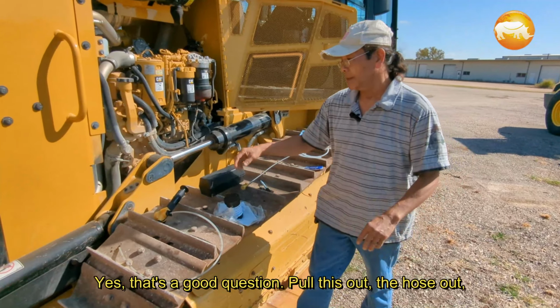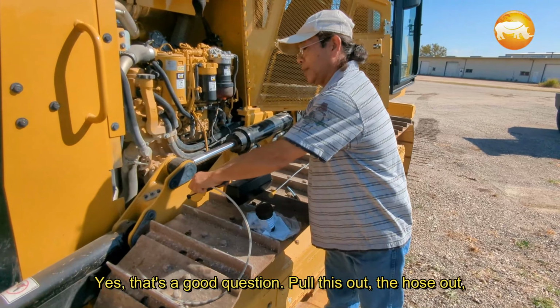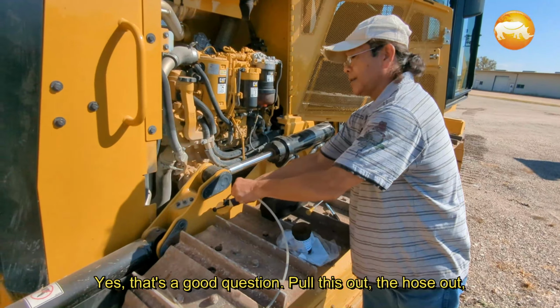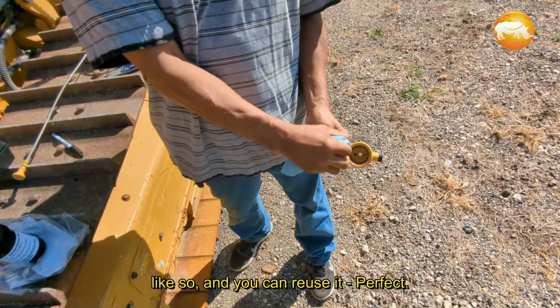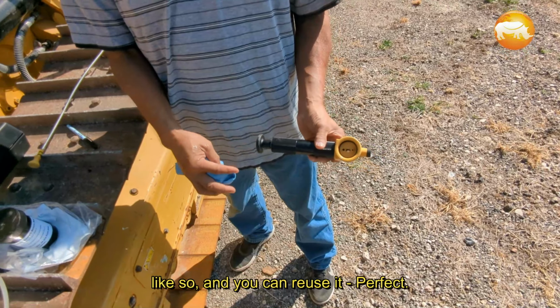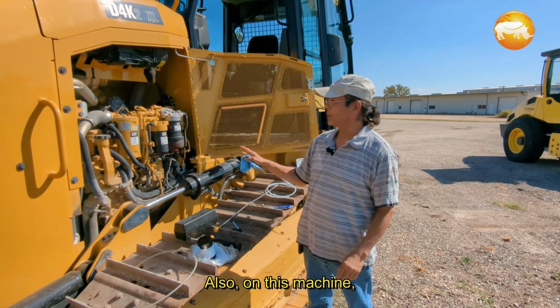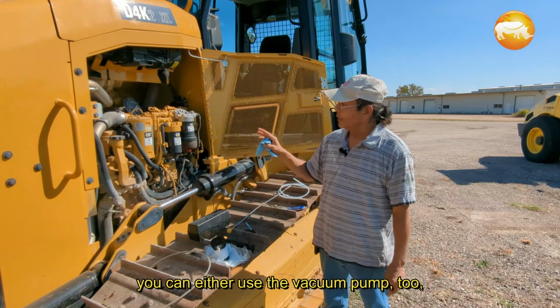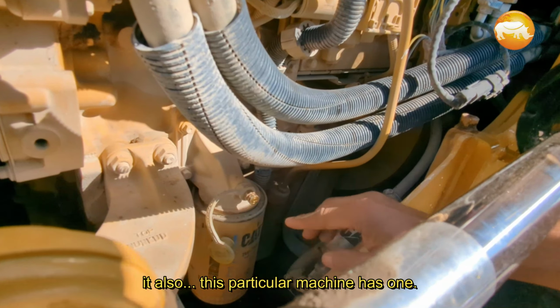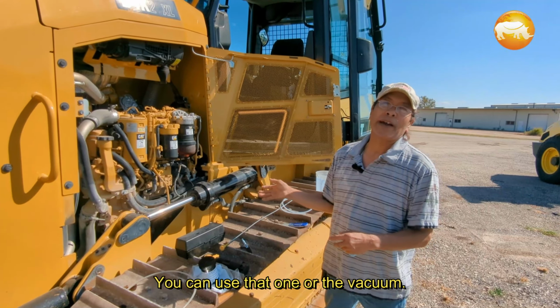So, Allan, is there anything we need to know about keeping the vac pump itself clean? Yes, that's a good question. Pull the hose out, and sometimes that O-ring right there will have residue, or those little ports. Take a clean rag, just wipe it off, like so, and you can reuse it. Perfect. Also on this machine, you can either use the vacuum pump tube, or you can use the probe port. This particular machine has one. So either way, you're going to get a sample. You can use that one or the vacuum.